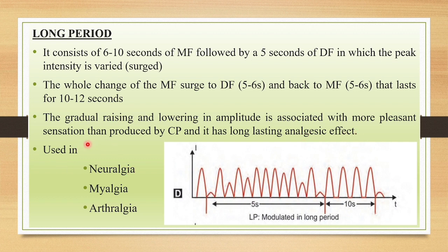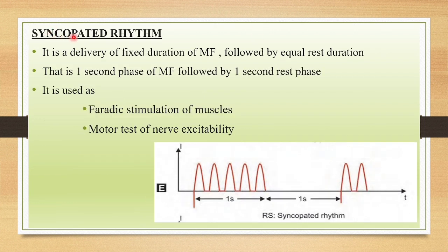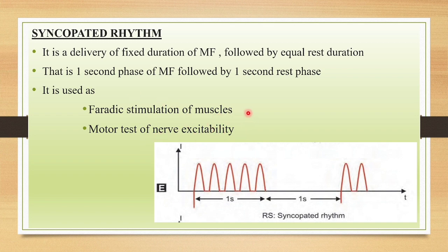The long period mode is mainly used for treating pain-related issues like neuralgia, myalgia and arthralgia. The last mode is syncopated rhythm — a delivery of fixed duration of monophase followed by an equal rest duration. One second of monophase is followed by one second of rest period. This can be used for faradic stimulation of muscles and motor testing of nerve excitability.